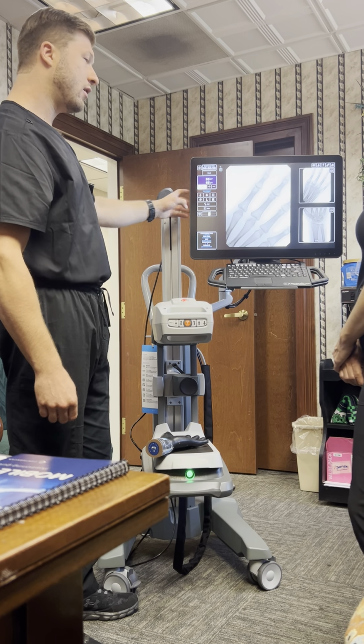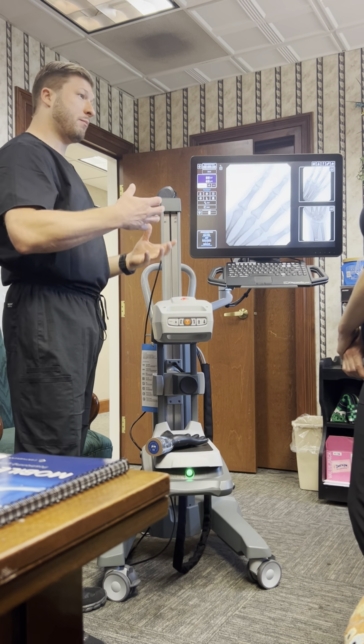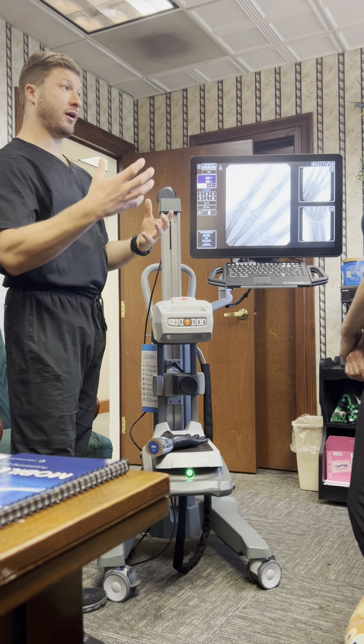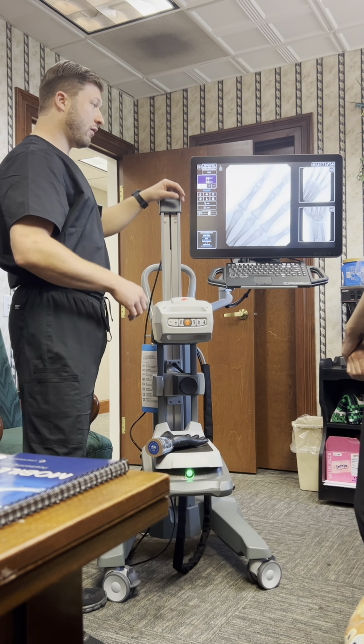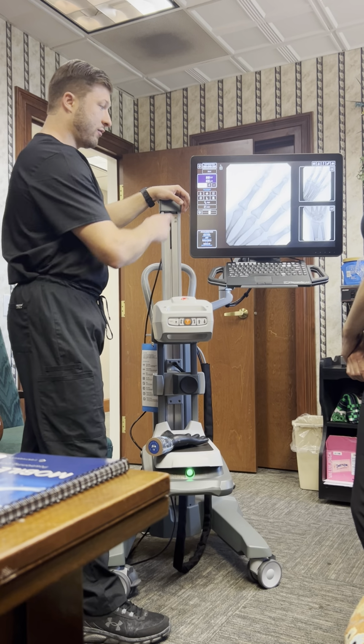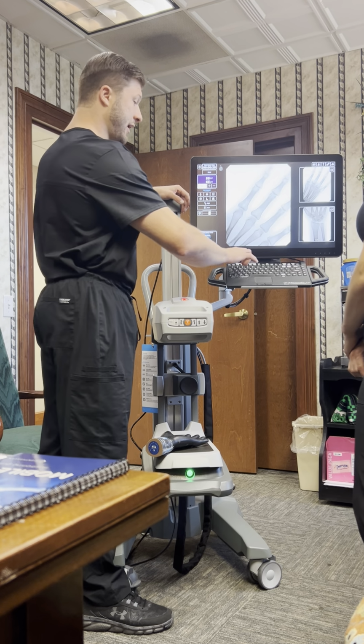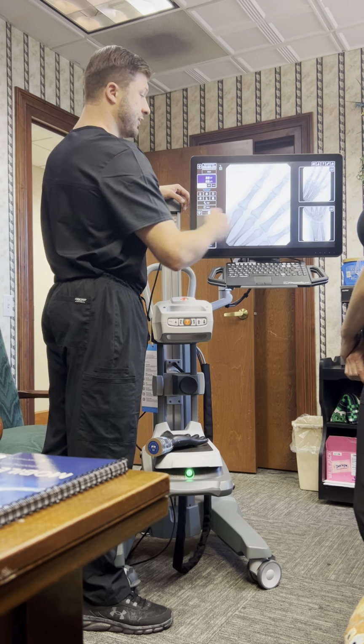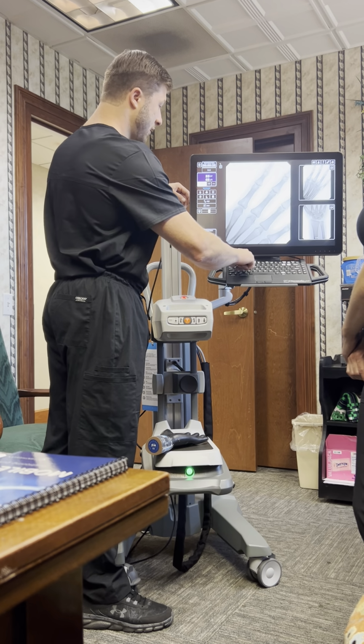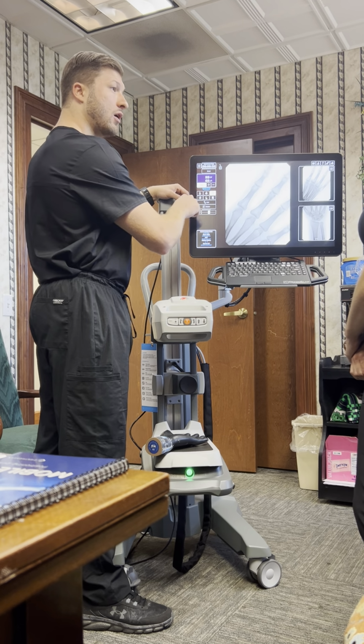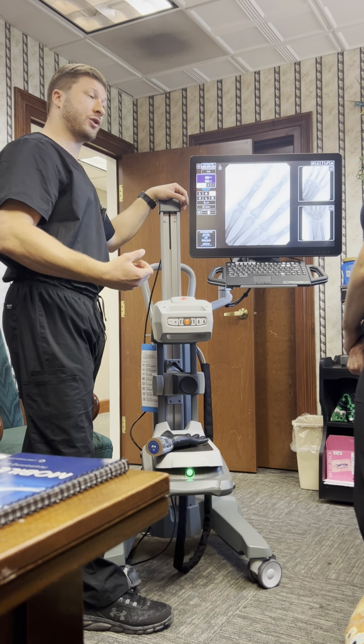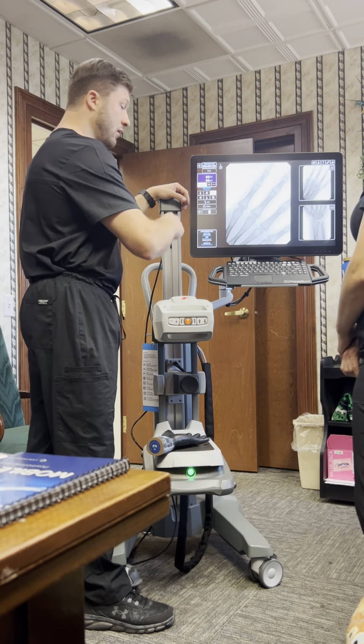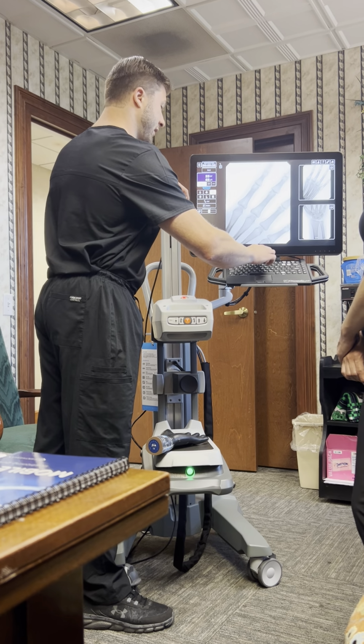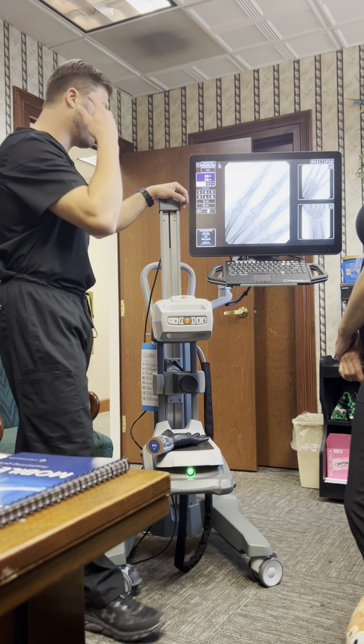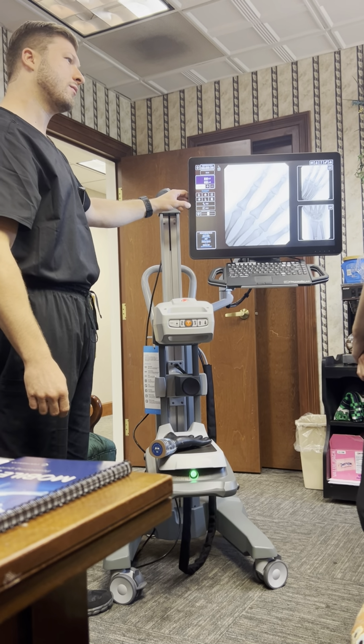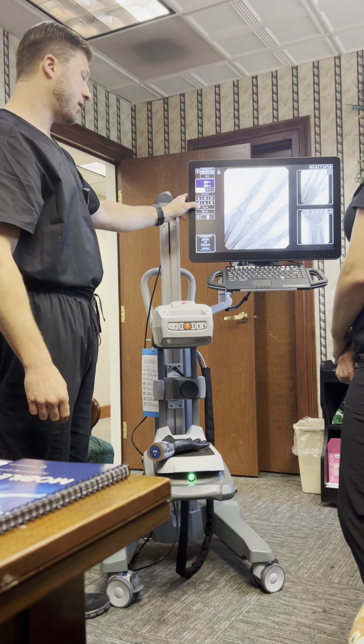Low sits in low because it's a great middle ground between static imaging and fluoroscopy. If we're going to take a fluoroscopic loop and we have it in high, watch when I hit DVR, which is essentially telling the device I want to take a fluoroscopic loop, it'll sit it back down into low, because it knows it's not going to be an optimal fluoroscopic loop if this is in high. So that's probably the only function that you'll need to keep in mind, but it does it for you anyways. So I'm going to put it back into low.